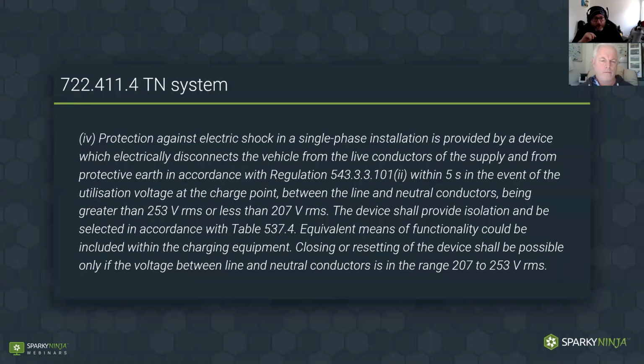The new one, this one's had a lot of debate. And this one says, first of all, single phase. So protection against electric shock in a single phase installation is provided by a device which electrically disconnects the vehicle from the live conductors of the supply from the protective earth in accordance with 543.3.3.101. The same thing, must disconnect the CPC after and then make it before within 5 seconds.